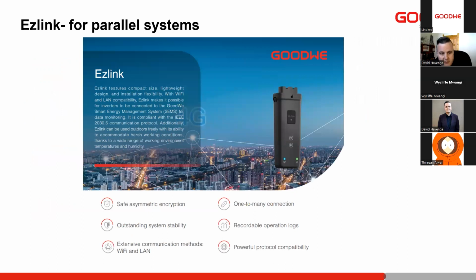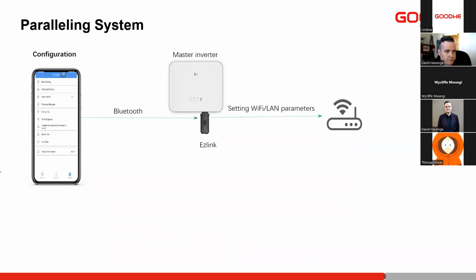So this is just a look at the Ezlink. It's the only optional accessory that you will need for paralleling the ES generation 2 device. So please keep in mind, you do need this for parallel. The Ezlink also has built-in Bluetooth. The Ezlink has LAN as well as Wi-Fi. And in the parallel system, we do not have any Wi-Fi modules connected to any of our inverters. We only have the Ezlink connected to the master inverter. All the communication will be handled for the entire plant via the Ezlink.